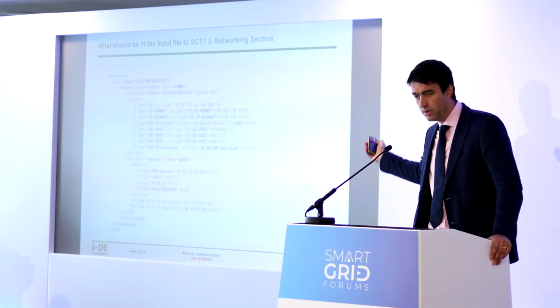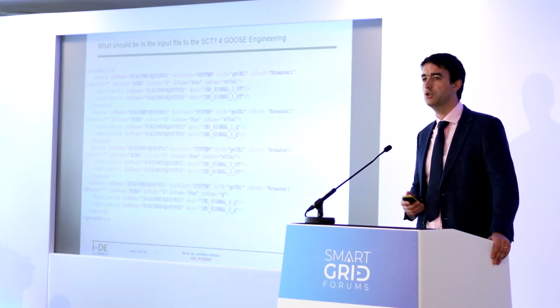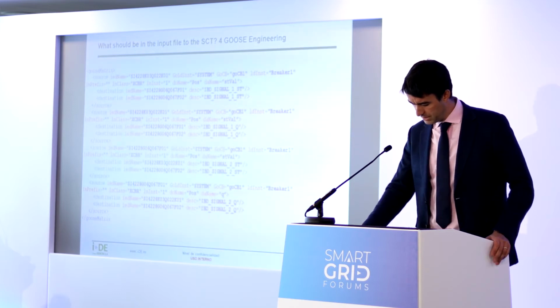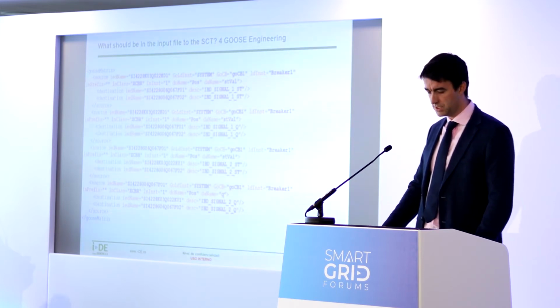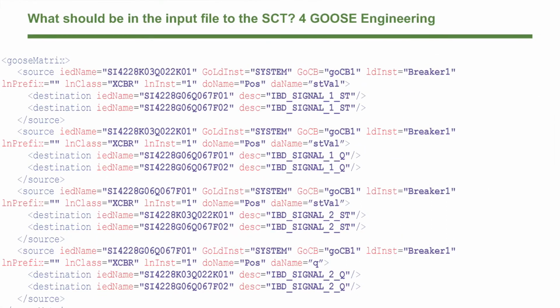You might wonder how we can automate the Goose engineering, which depends not only on the publishing of the messages, but also on the standardized configuration type, and relies upon the particular topology of that substation to know what has to make the subscriptions. The answer is that our central SAS systems know the topology, can understand it, and can make up a Goose matrix using the later binding method, which is in edition 2.1.